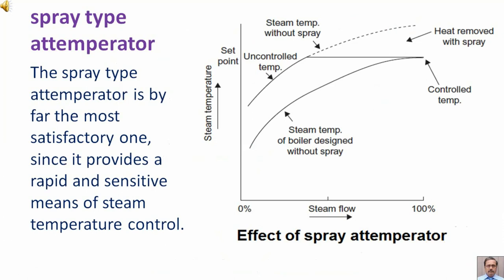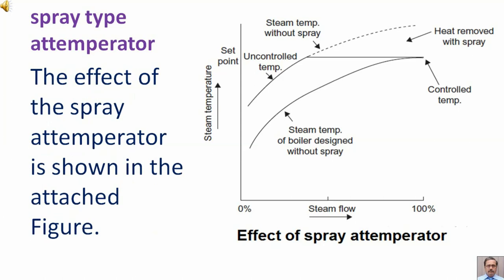The spray type attemperator is by far the most satisfactory one, since it provides a rapid and sensitive means of steam temperature control. The effect of the spray attemperator is shown in the attached figure.